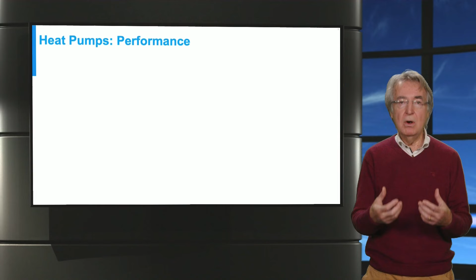This graph shows the variation of COP along the y-axis and sink temperature along the x-axis for a fixed source temperature. The green curve shows the COP of the actual heat pump, while the blue curve is the reversible COP of the heat pump. For this case, the environmental air at 0 degrees Celsius is taken as the heat source. For the heat sink temperature of 40 degrees Celsius, we get a COP of about 3.1. If we use groundwater at 10 degrees Celsius as heat source, the COP becomes 4.2.